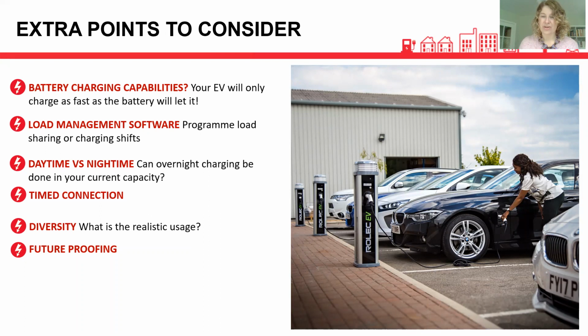Also, if you are considering slower chargers for overnight, but maybe faster chargers for any quick top-ups during the day, you don't have to add those two loads together, because they're being used at different times. So if it's highly unlikely that those two charges will ever be used at the same time, don't double count the load.